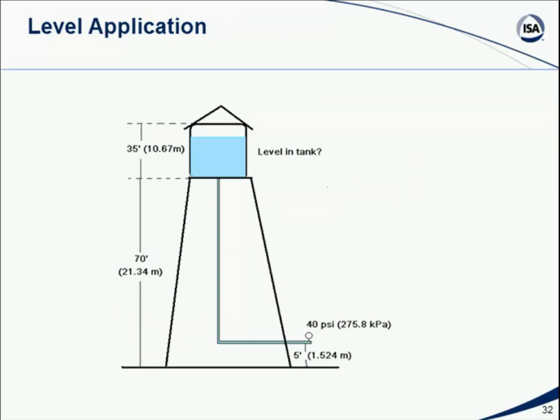All right, let's take a look at an actual typical level measurement application. If you're in the water waste industry, or just happen to like to drink water and be able to turn your faucet on, then you've probably noticed somewhere in your neighborhood these big above ground water storage tanks. They may be the golf ball shaped tanks or an older tank that looks like this, but these tanks hold water up above ground level at a certain elevation in order to generate a certain pressure so that the water can push its way through all the pipes and into your home and up to your second floor or third floor. So the question here would be, if I want to know the level in this tank up here above ground, can I determine that level down here at ground level by taking a pressure measurement on this pipe down at the base of the tank?